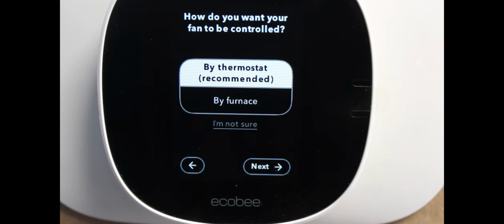How do you want your fan to be controlled? It's defaulted to use the thermostat to control the fan. If you have a gas appliance, whether it's a gas with straight AC or it's a hybrid unit, so it's a heat pump with a gas appliance, you would use the furnace. Furnaces, gas or liquid propane appliances, have their own circuit board with their own on and off delays, so we would use that in those cases. Heat pump with electric heat, in this case, we're going to be using the thermostat.